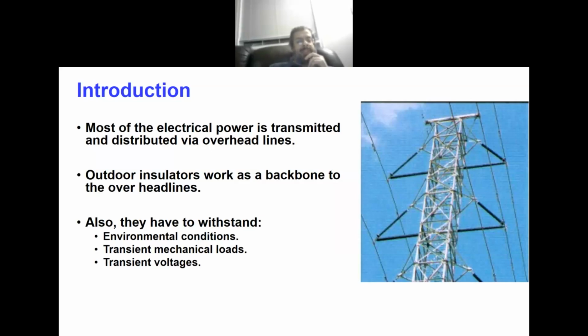If they cannot do this job, then there will be a flashover or an arc from the high voltage to the grounded tower. Now, these insulators have to do this job under severe environmental conditions, like the ones we have in Qatar—under humidity, UV, sun, and heat. So there are many factors that influence their performance.